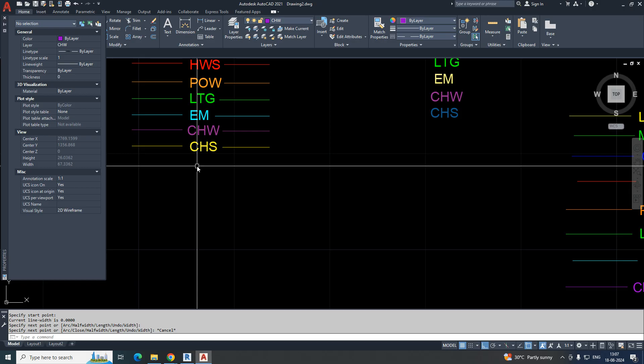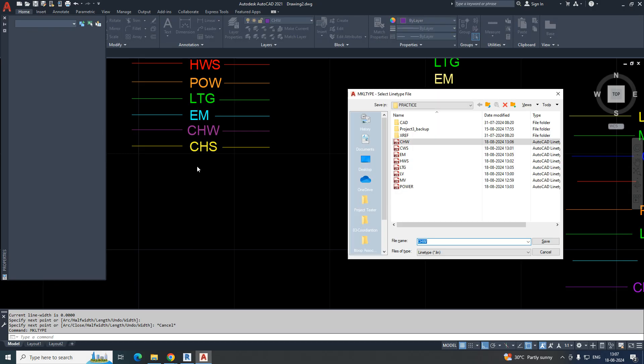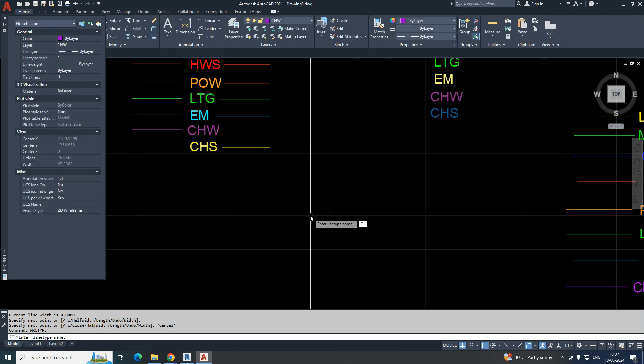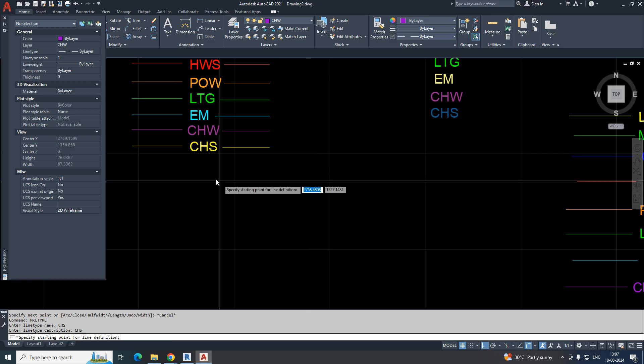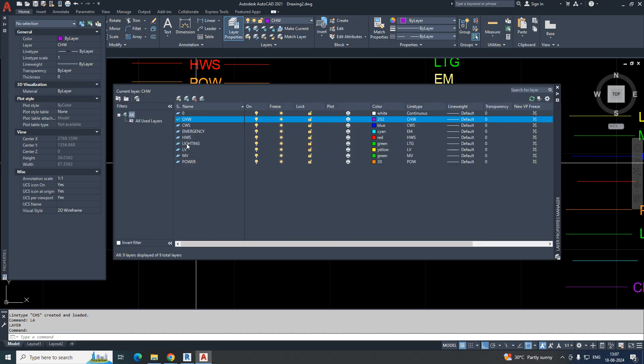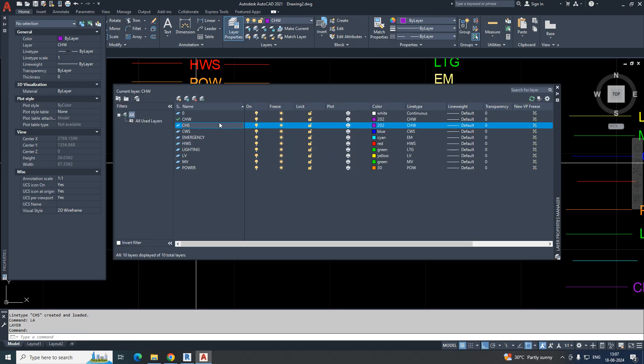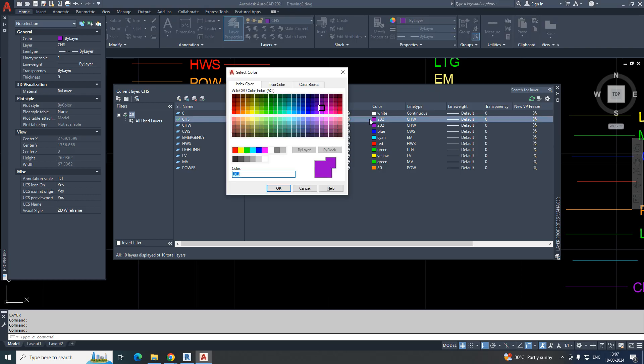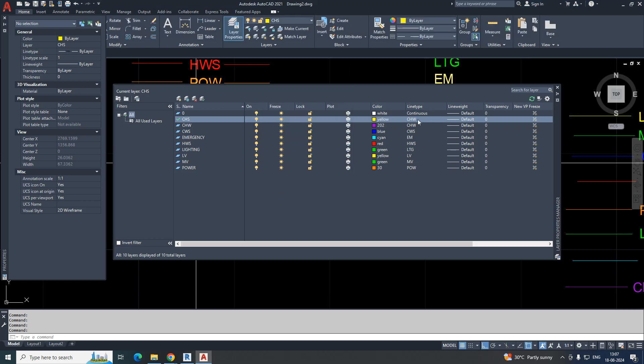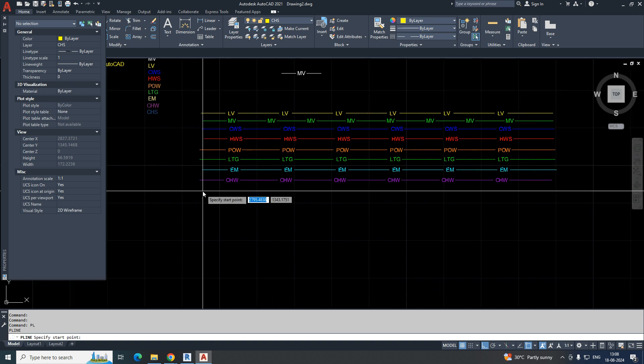One more — CHS (chilled water supply): run MKLT, name it 'chs,' save it, give description 'chs.' Select the two points of the line and it will create automatically. Create a new layer 'chs,' make it current, assign yellow or whichever color you like, change to the 'chs' line type, and draw — the new line type will be created.